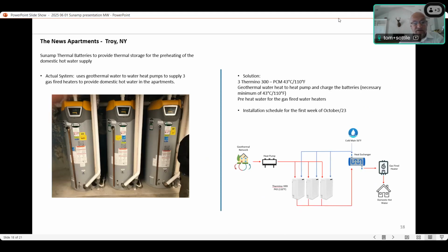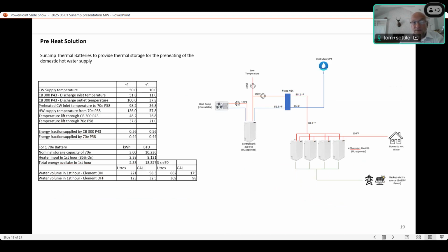Another project we did under the NYSERDA grant is where we had a 200 apartment building in Troy, New York, where they have a geothermal system to do heating and cooling in the building, but it's not sufficient to provide the peak demand for hot water. So they have 3 gas-fired water heaters. We use a standard water-to-water heat pump, R-410A, so it can only reach about 120 degrees. So here we're using a cooler PCM that actually melts at 110. And we're taking energy out of the loop. In the summertime, this is improving the efficiency on the cooling side. We're storing that energy up and using that as a preheat to the gas-fired water heaters. And we found a 50% reduction in the amount of gas consumed by doing this, because the gas heaters are now only heating the water from 100 to 140 instead of from 50 to 140.